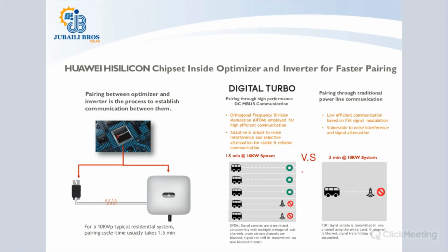Unlike the traditional system where there's only one route of communication. So if that route is blocked, there's a problem. Here you have multiple routes of communication, and even if 2 or 3 of them are blocked, there are still ways that the inverter can actually communicate with the PV optimizer. And this is to increase the rate of pairing and the rate of shutdown in any communication system between the PV optimizer and the PV inverter. In this case, we see 1.5 minutes for a 10 kilowatt system versus 3 minutes or so for an ordinary or traditional system.